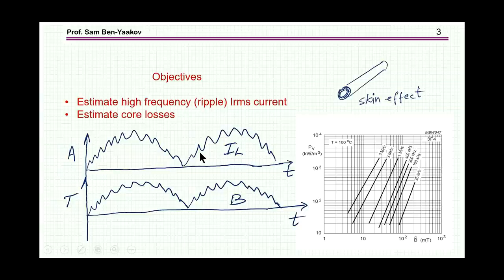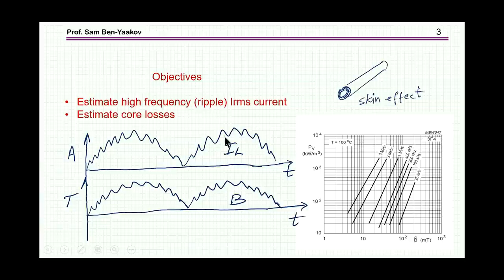The objective of this video is to estimate by simulation the high frequency ripple component of the inductor current. The inductor current contains both a low frequency and high frequency component. The high frequency component is important because of the skin effect. As the current becomes higher, we're going to use thicker, larger diameter wire. If this is a solid wire, then we're going to have the skin effect, and the high frequency component passes through this portion. So if this high frequency component is appreciable, then we have to consider the use of Litz wire.